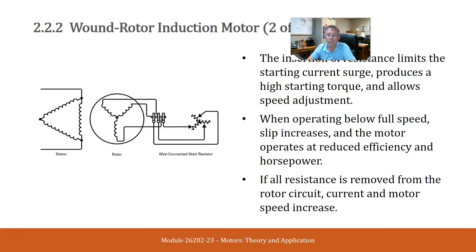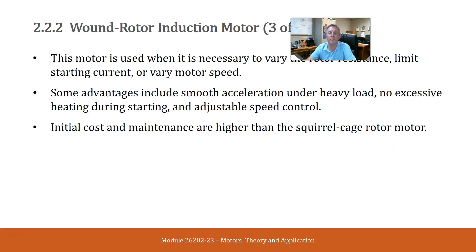If all resistance is removed from the rotor circuit, current and motor speed increase. This motor is used when it is necessary to vary the rotor resistance, limit starting current, or vary motor speed. Some advantages include smooth acceleration under heavy load, no excessive heating during starting, and adjustable speed control. Initial costs and maintenance are higher than the squirrel cage rotor motor.